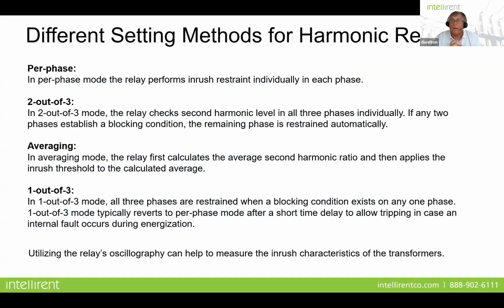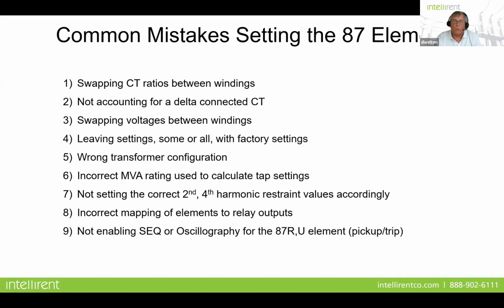Now, there's a bunch of different ways to set a harmonic restraint. It's per phase, and in that case, the relay performs a restraint on any of the three phases. 2 out of 3 means that it must restrain if it sees it on 2 out of 3 phases. And then some relays will do an averaging. In that averaging mode, the relay first calculates the second harmonic ratio and then applies the inrush threshold to a calculated average. In 1 out of 3 mode, all 3 phases are restrained when a blocking condition exists for only any one phase. So 1 out of 3 mode typically reverts to per phase mode after a short time delay, and that will allow tripping. Basically, it can be done either way, and it's important to realize that these are all settings in the relay, and this right here will help define what those settings mean. It's always a good idea to refer to your protective relay manual to find out.